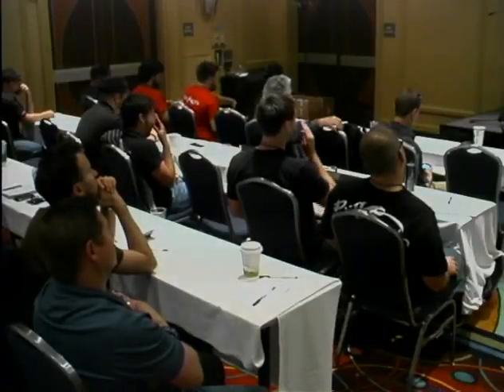On integrating with alarm systems — have you found any legal or insurance issues integrating with, say, ADT? The easiest way to make that happen is to ask for a dry contact loop. Most alarm vendors are okay with giving you an on-off contact that, when you break that connection, trips the alarm. People use that for things like monitoring a freezer so you don't lose $10,000 worth of seafood, or detecting if your basement is flooded. Generally they're friendly with that — they don't care what's on the other end as long as it doesn't put high voltage in or screw up their system. Any quality system installed by a pro should be able to do that, and most have a panic button control you can tie into.